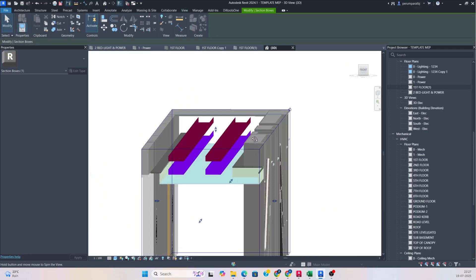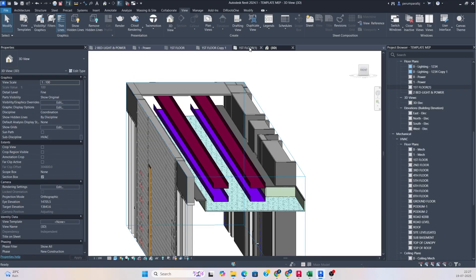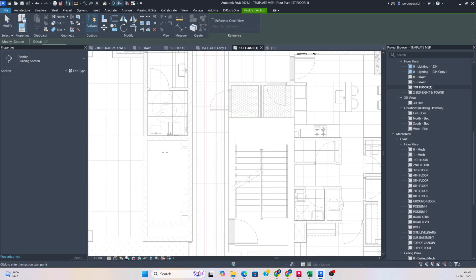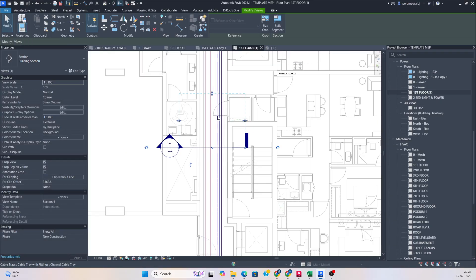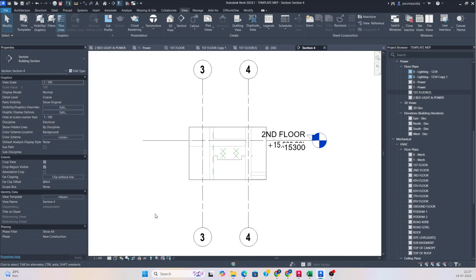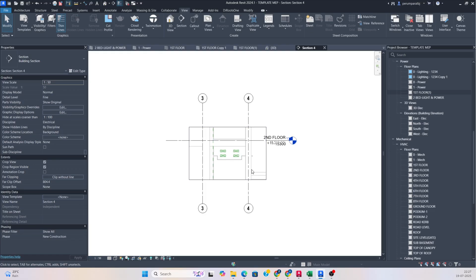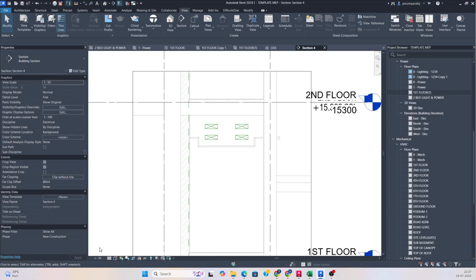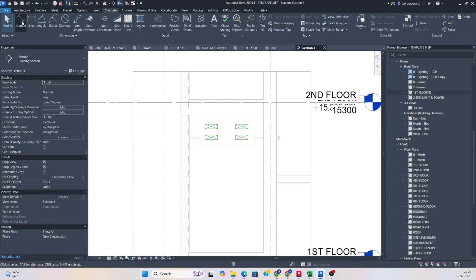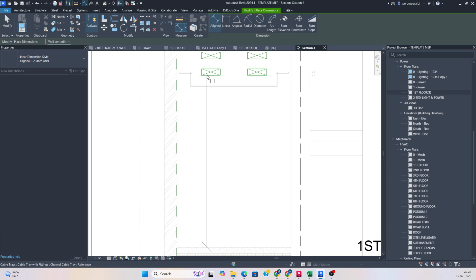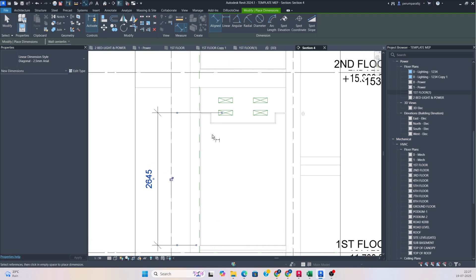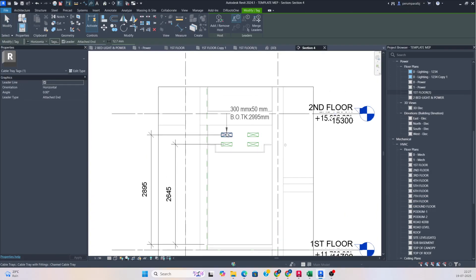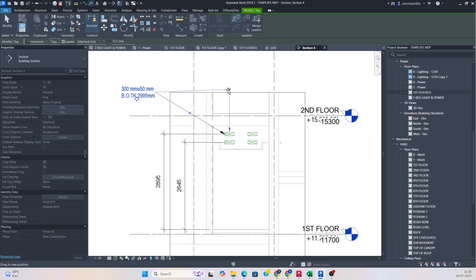You can see the cable trays are running in parallel — this is the method for making cable trays go parallel in a small corridor. You can also create a section, stretch it up to here, then go to View and give a scale of around 1:50, set fine detail so the cable tray is clearly visible. You can give dimensions and annotations — go to Annotate, take annotations, and give the dimension for the bottom of tray. You can also add tags wherever needed.